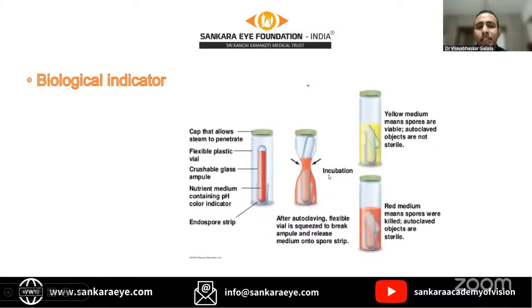Once you receive it after the sterilization process is completed, squeeze this vial. It breaks the glass ampoule, and the medium comes out and mixes with the spore strip. Now you send it for incubation. After that, if you observe any growth of this bacteria, there will be a change in the color. That means the bacteria remain viable, that is, alive, so the sterilization process was not effective in killing the bacteria. If there is no change in the color, the bacteria are already killed, so the autoclaved objects are sterile and we can accept them.